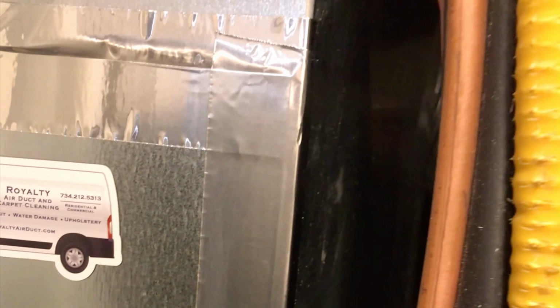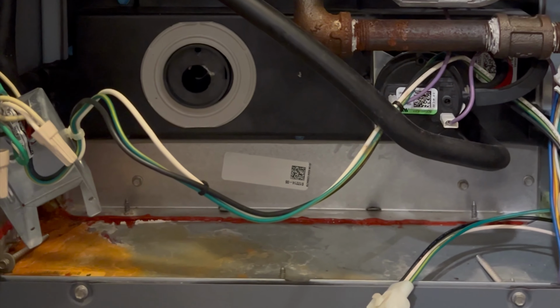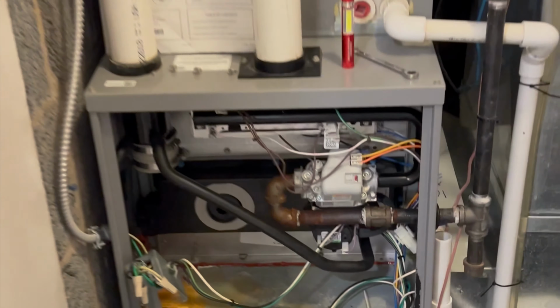And it's always a sign, if you hear noises in your HVAC which you haven't heard before, that something is wrong. And in my case, I knew it starts before the burners start, so I could pinpoint it to the inducer fan. And what that does, I'll explain at the end of the video.